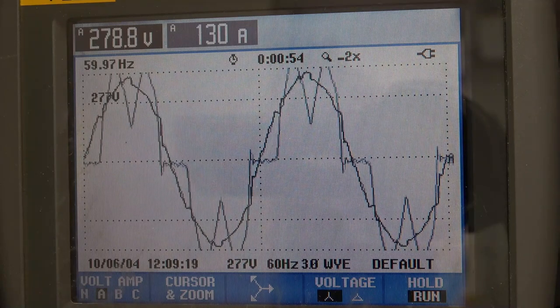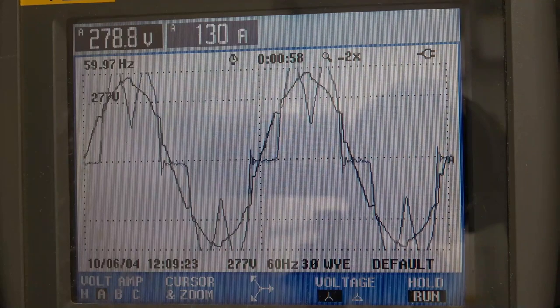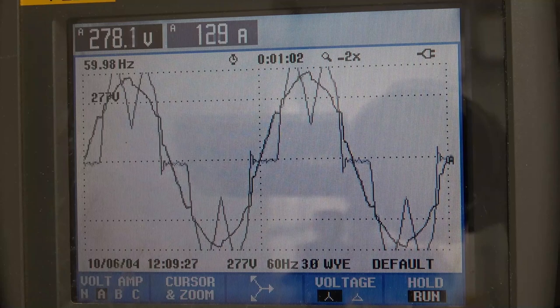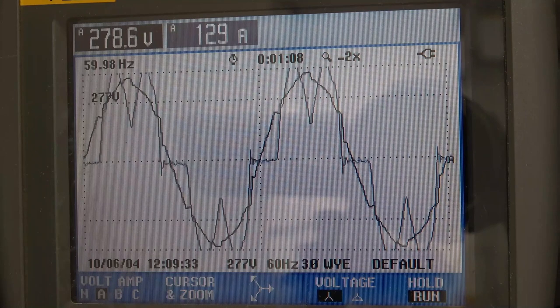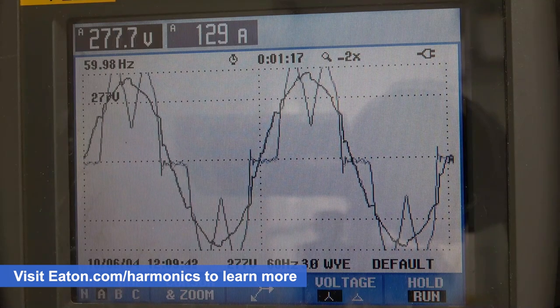Linear load is going to be clean sine wave voltage. Current that's drawn, like from a regular cross-line motor or a light or something like that, is going to look like the voltage. Maybe a little bit leading, maybe a little bit lagging, maybe in phase, depending on the power factor of the load. Non-linear load, the current doesn't look like the voltage. And the more current distortion I add, the more voltage distortion I get.